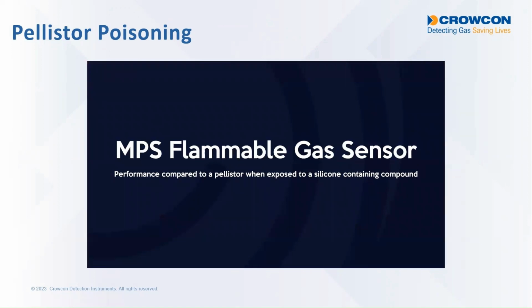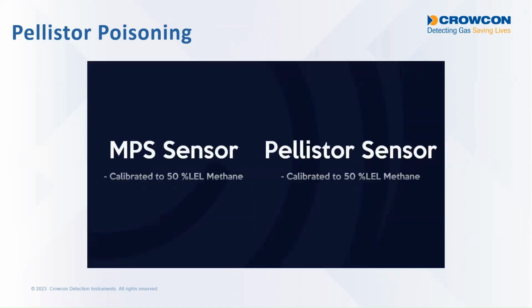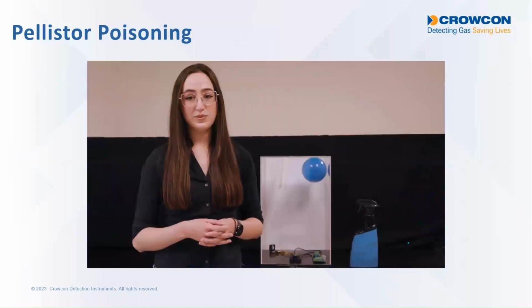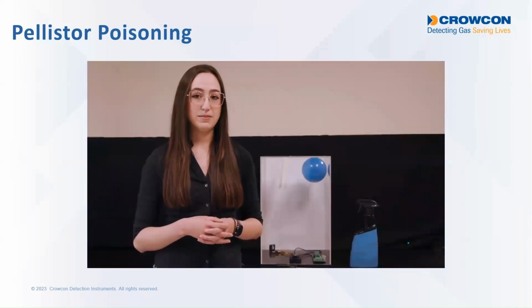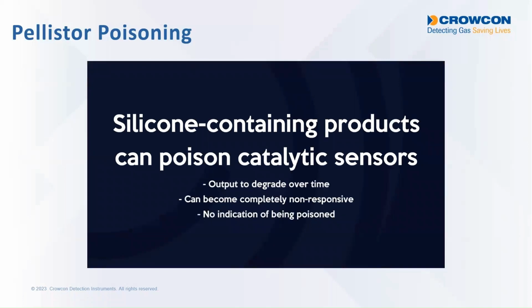So we're going to demonstrate the poison resistance of the MPS sensor compared to a Pellistor sensor. They're both calibrated for methane, although as I've already said, the MPS sensor will also respond very accurately to hydrogen gas. So we have a chamber that has a Pellistor sensor and an MPS sensor inside, and we have a balloon that's filled with methane. And this test is to demonstrate the vulnerability of Pellistors to poisoning from a silicone product, and to demonstrate the MPS sensor is not poisoned by the same compound.